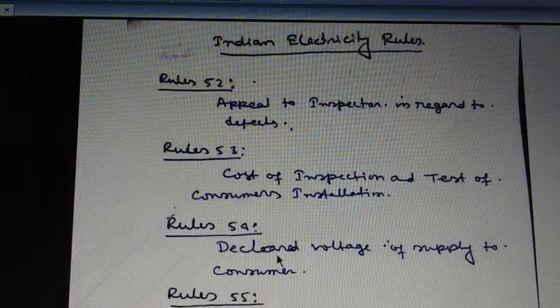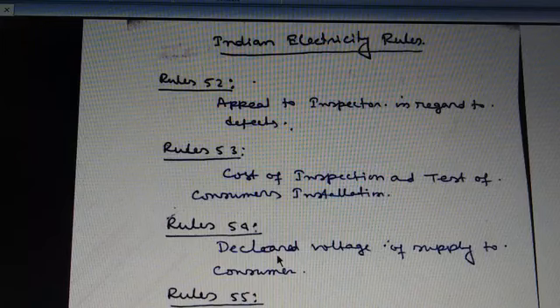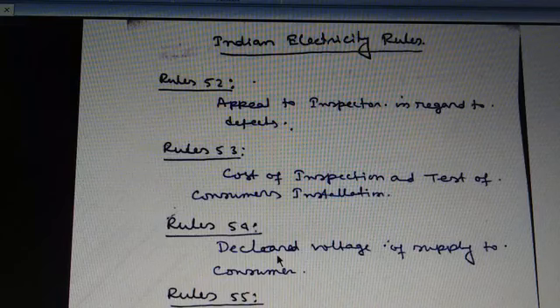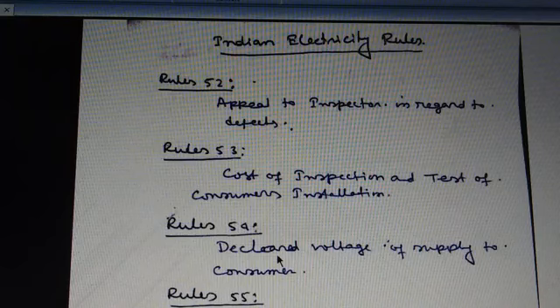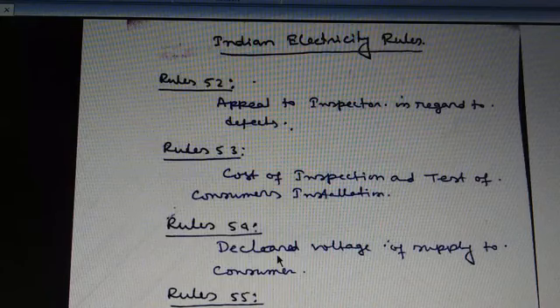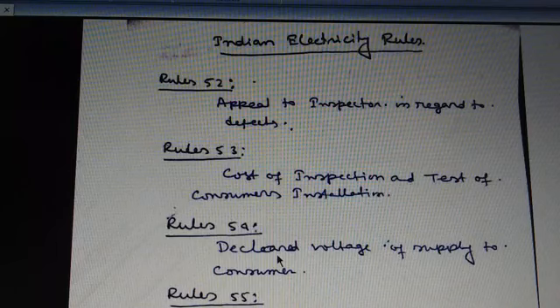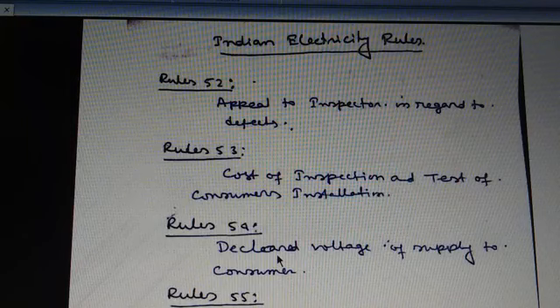Next, rule number 54. Rule number 54 is related with the declared voltage of supply to the consumer. Except with the written consent of the consumer or the previous approval of the state government, a supplier shall not permit the voltage at the point of commencement of supply, as defined under rule 58, to vary from the declared voltage by more than 5% in the case of low and medium voltage, and by more than 12.5% in case of high and extra high voltage. So these are the limitations.